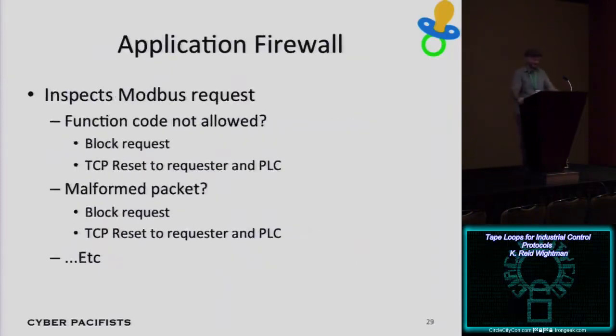The application firewall inspects the Modbus packet itself. It checks all the fields to make sure things look legitimate. For example, the length field is 2 bytes long, but the real packet length restriction is 255, so it checks that you're using a valid length field, and that the total data you're sending matches the length field. It can also make sure the function code you're trying to use is allowed. So when you try to send packets through the firewall that aren't allowed, it blocks the request.